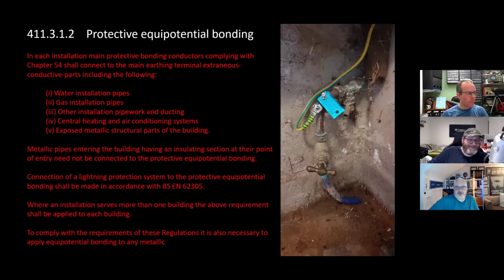Everybody should know this regulation, or hopefully refer to it in the big blue book, which is 411312, protective equipotential bonding. It states, currently - this is the existing regulation - in each installation, main protective bonding conductors complying with chapter 54 shall connect to the main earthing terminal extraneous conductive parts, including the following: water, gas, other pipework and ducting, central heating and air conditioning systems, and exposed metallic structural parts of the building. We obviously go to chapter 54 for sizing of said bonding conductors.